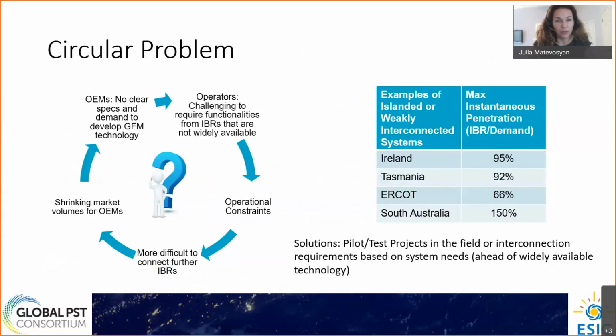You've probably seen this slide before from me. This is my favorite circular problem. As we integrate more and more inverter-based resources on the system, it becomes challenging for system operators to keep the system reliable and stable. It's also challenging to require additional functionality from inverter-based resources, which is not currently commercially or widely available. What it results in is that operators are forced to apply transmission constraints or other operational constraints. This leads to curtailments. It becomes more difficult to connect further inverter-based resources. Either it's not economic or it's not permitted by system operators in different systems.